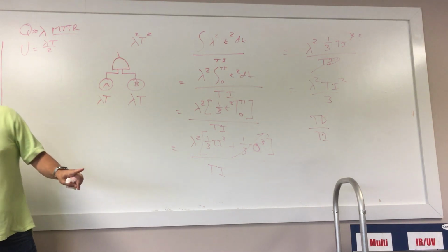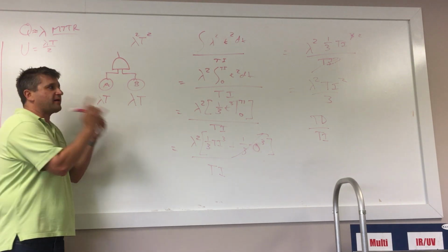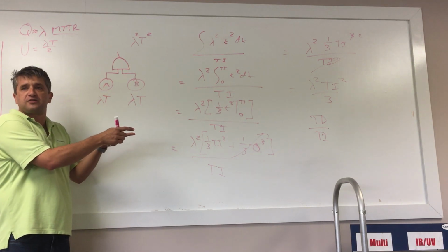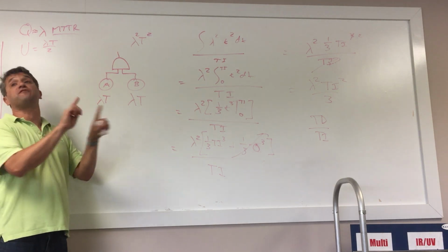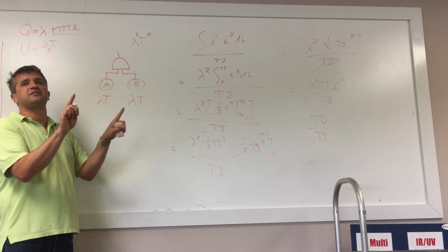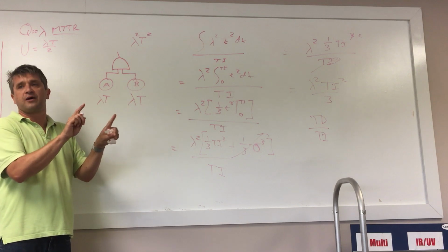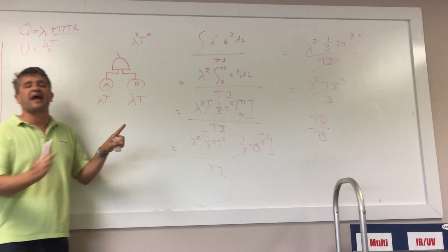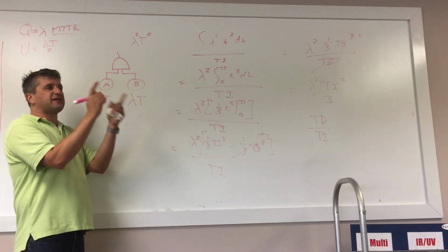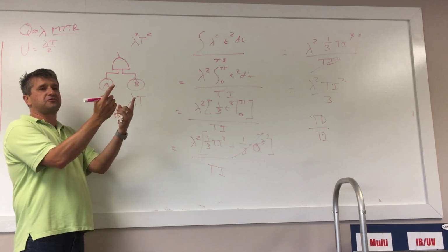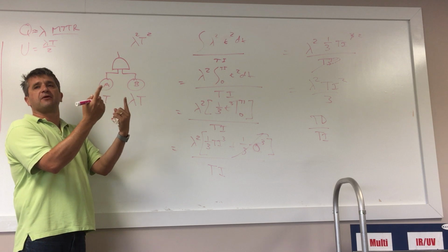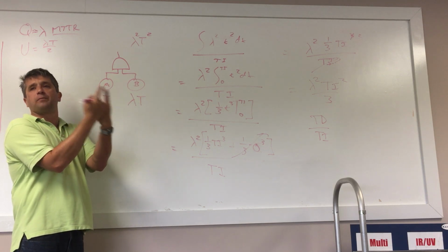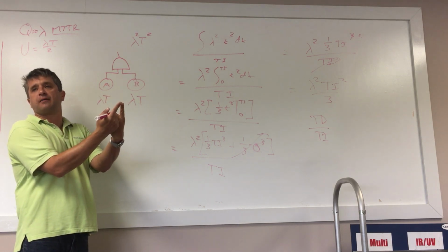First off, that equation assumes that we're not going to test both transmitters in a 1 out of 2 vote at the same time. It assumes we're going to test them at different times, and the time that we test them is completely random. So what that equation actually calculates is, if I test my 2 components in a 1 out of 2 system at random times, what is the probability that by accident I will be testing both of them at the same time?